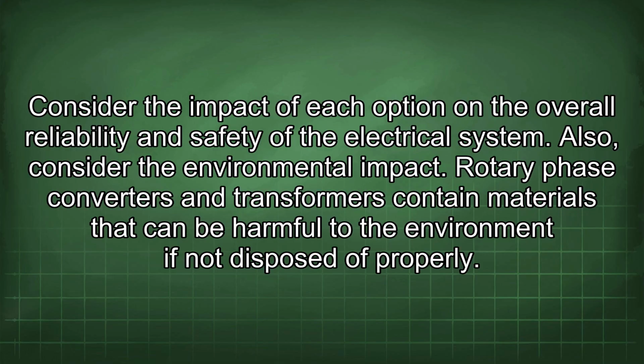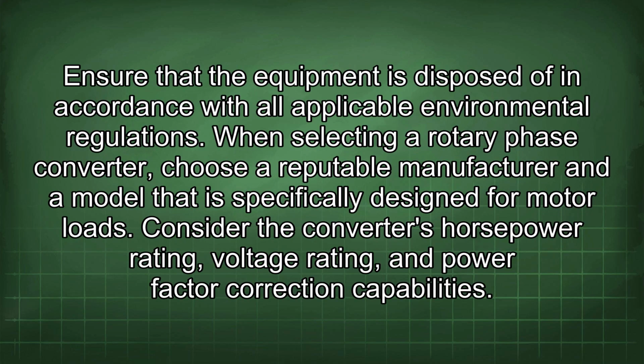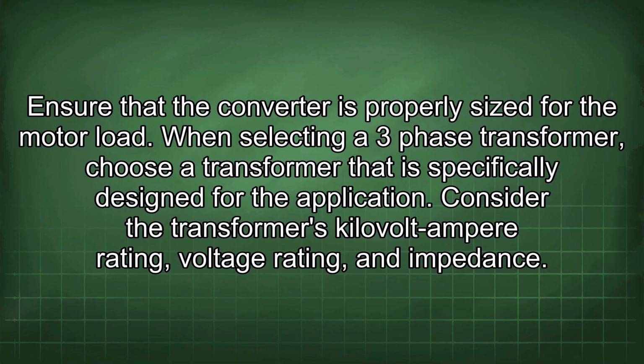Also consider the environmental impact. Rotary phase converters and transformers contain materials that can be harmful to the environment if not disposed of properly. Ensure that the equipment is disposed of in accordance with all applicable environmental regulations. When selecting a rotary phase converter, choose a reputable manufacturer and a model that is specifically designed for motor loads. Consider the converter's horsepower rating, voltage rating, and power factor correction capabilities. Ensure that the converter is properly sized for the motor load.